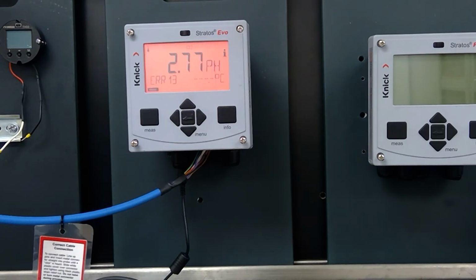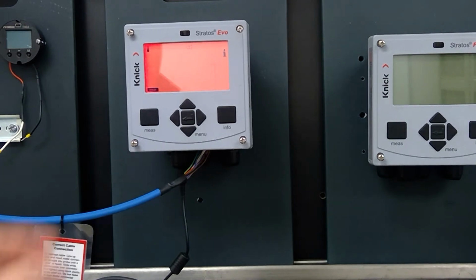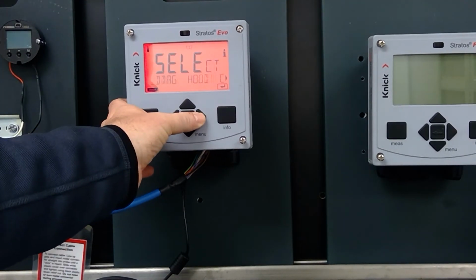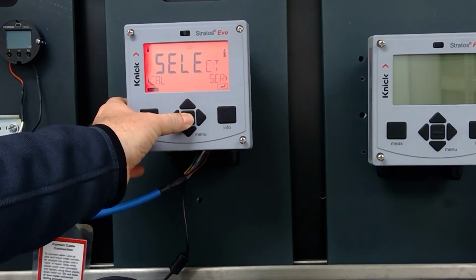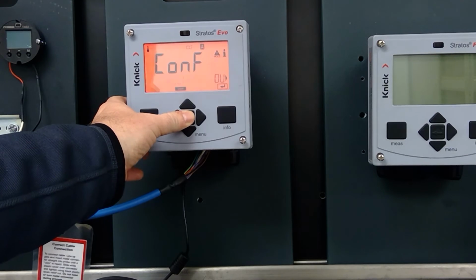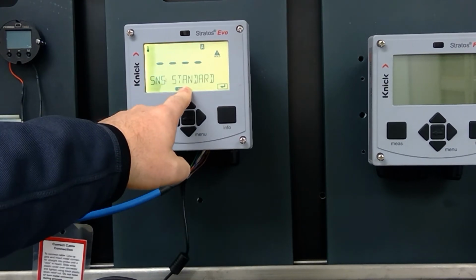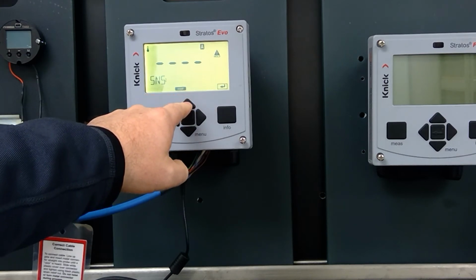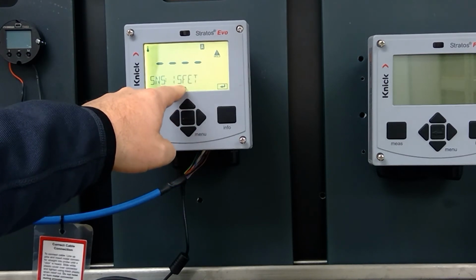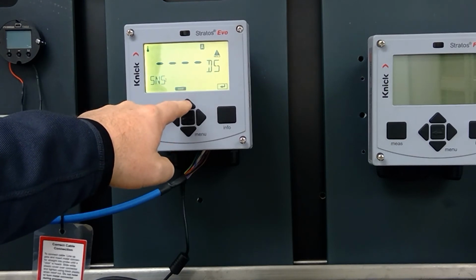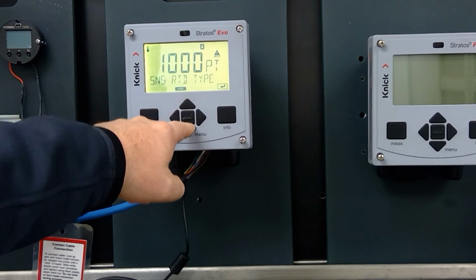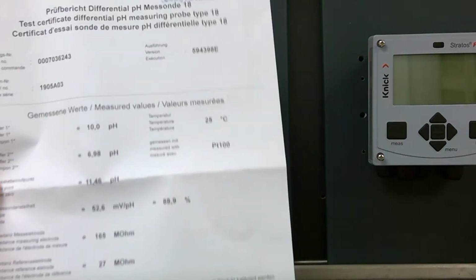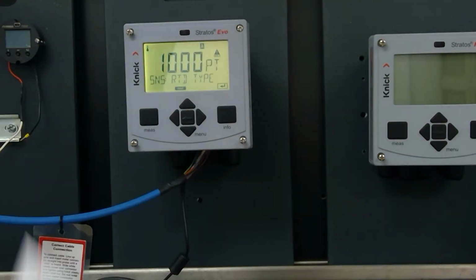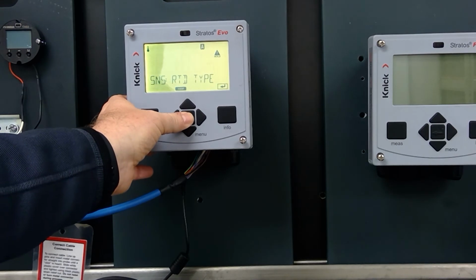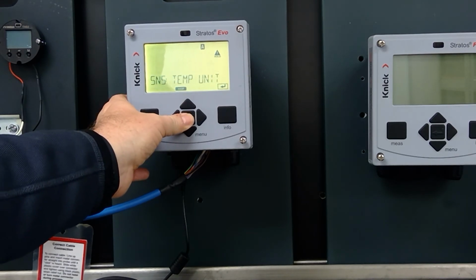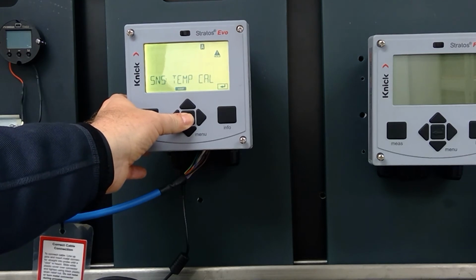So let's go ahead and go into the configuration. What I do is I hit menu, go to configure, Parset A, sensor. So we're already set up for analog. That's what standard means. But if for some reason you were taking an existing transmitter that was set up for a different type of technology, like what you're seeing here, you just need to change it to standard. The next thing is, the Pfaudler Type 18 has a PT1000 RTD, and this is right on your test certificate.